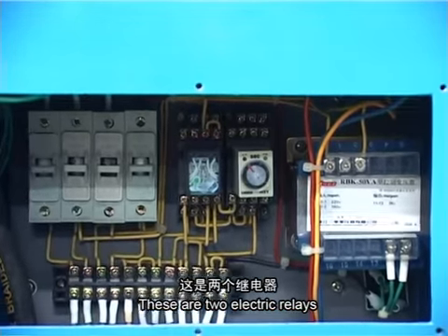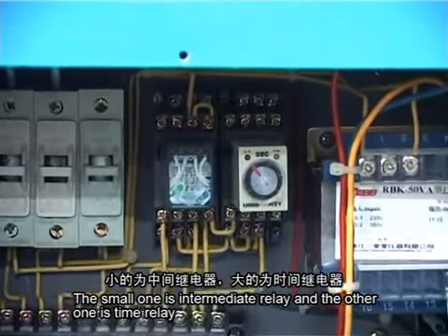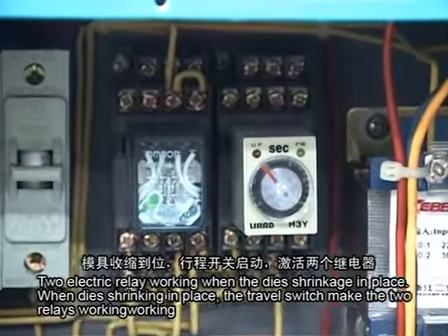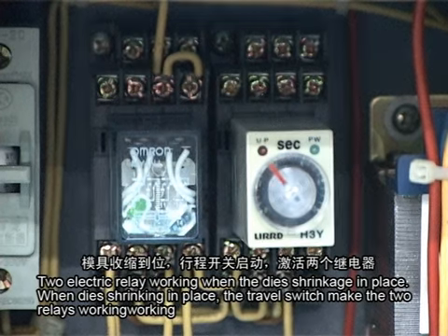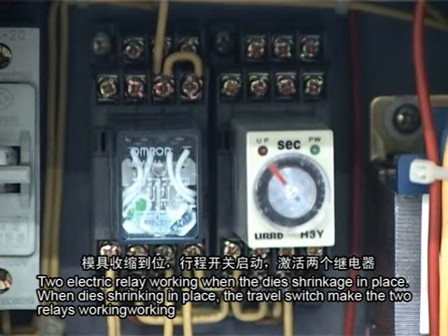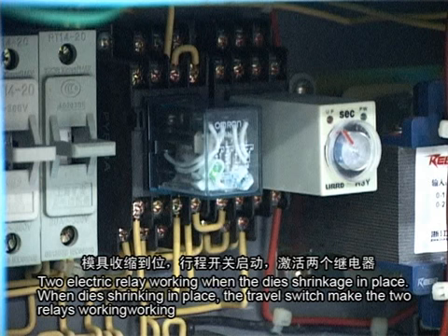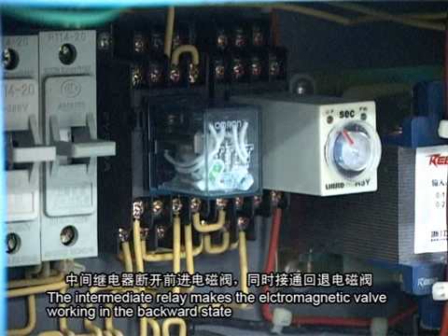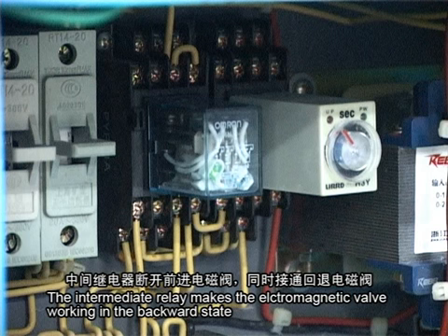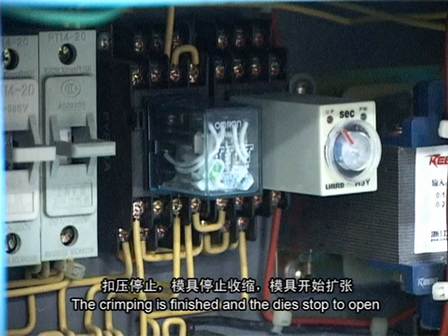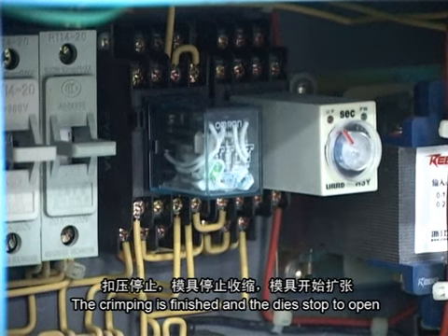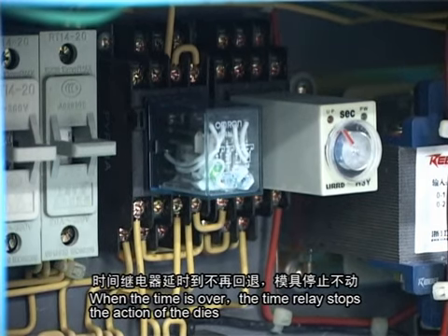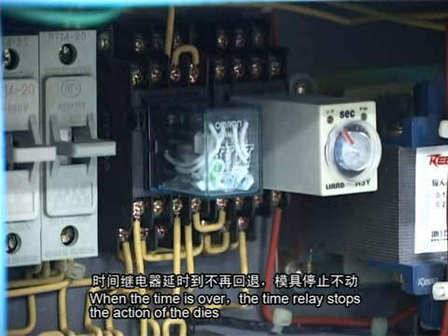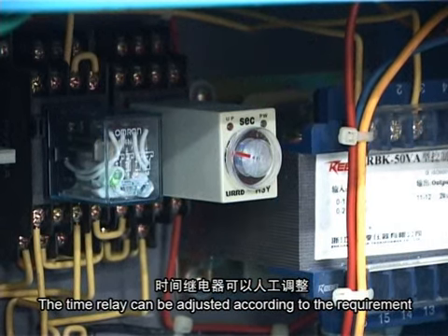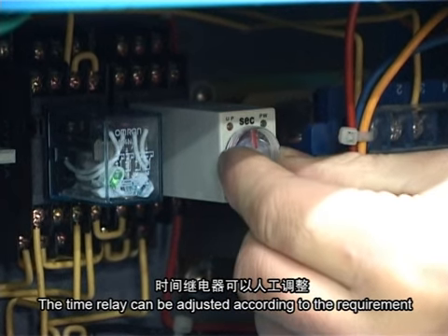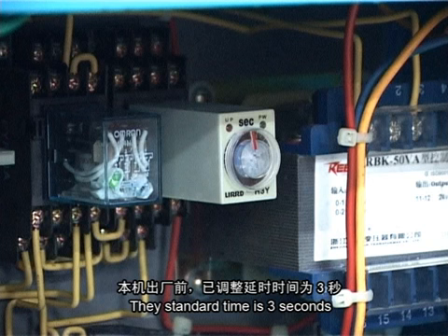These are 2 electric relays. The small one is the intermediate relay and the other one is the time relay. The 2 electric relays work when the dies shrink in place. When the dies shrink in place, the travel switch makes the 2 relays work. The time relay starts timing. The intermediate relay makes the electromagnetic valve work in the backward state. The crimping is finished and the dies start to open. When the time is over, the time relay stops the action of the dies. The time relay can be adjusted according to the requirement. The standard time is 3 seconds.